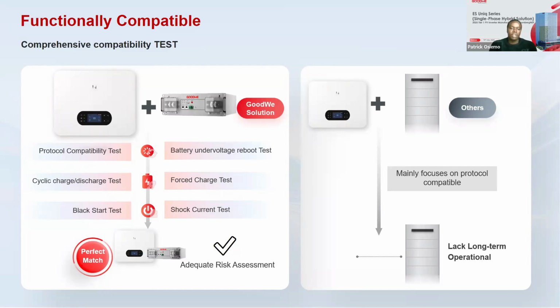And when I say in-house, the products that we are releasing into the market go through a number of tests. So one of the tests that we do is the product test. In case it's a battery, we'll check the under voltage or rebooting test, the forced charge test, the shock test, the black start test, the protocol compatibility test. So we do all these tests in-house before releasing the product into the market. So our procedure is basically to do a beta test and ensure that the product is well operating and they are of a perfect match. Perfect match from the battery to the inverter, to the communication protocol, to the communication of monitoring portal.